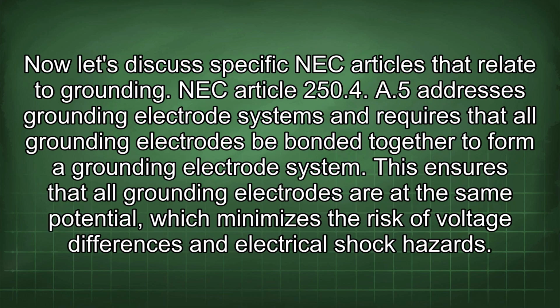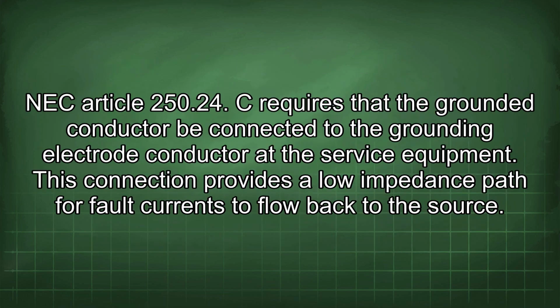Now let's discuss specific NEC articles that relate to grounding. NEC Article 250.4 A5 addresses grounding electrode systems and requires that all grounding electrodes be bonded together to form a grounding electrode system. This ensures that all grounding electrodes are at the same potential, which minimizes the risk of voltage differences and electrical shock hazards. NEC Article 250.24 C requires that the grounded conductor be connected to the grounding electrode conductor at the service equipment. This connection provides a low impedance path for fault currents to flow back to the source.